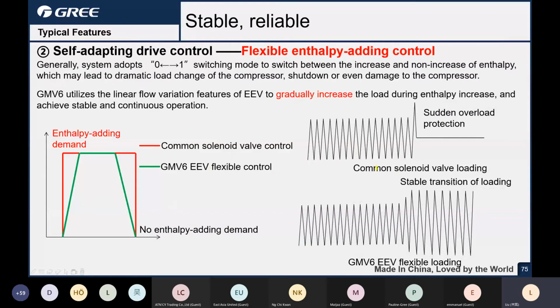So, for example, for the common solenoid valve, if there is an EVI control at the moment, okay, that looks like this. But if some problem, okay, it's shut down immediately, abruptly, right? So actually, this is not good for the units running. However, for GMV6, even some change of the compressor demands, it will adjust. It will adjust the opening of the EVI expansion valve to make the control more flexible. Okay.